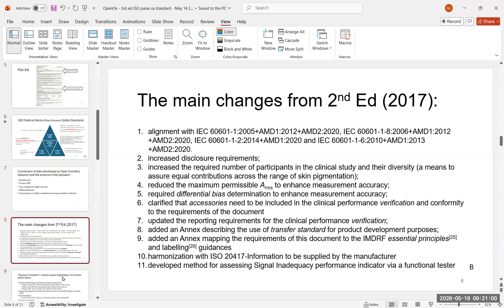But when it comes to accuracy performance, it's all based upon adult volunteers being put into a controlled desaturation study over the declared range of a medical device pulse oximeter declared displayed saturation, so 70 to 100%. So this list obviously is taking in a lot of other issues.